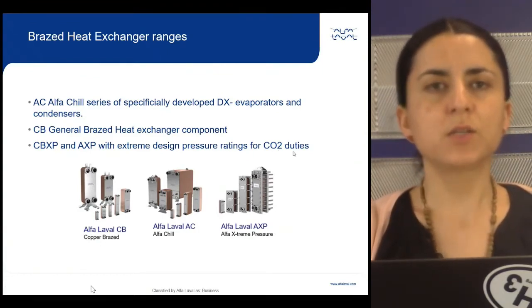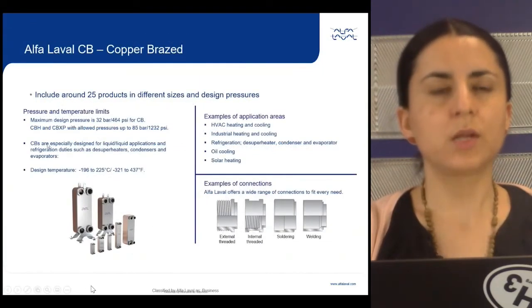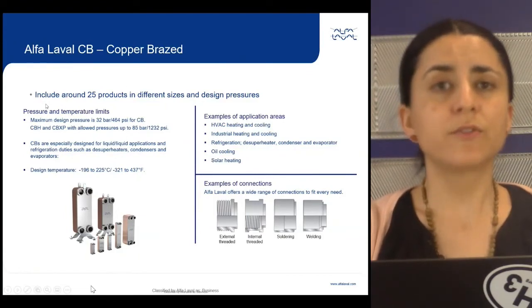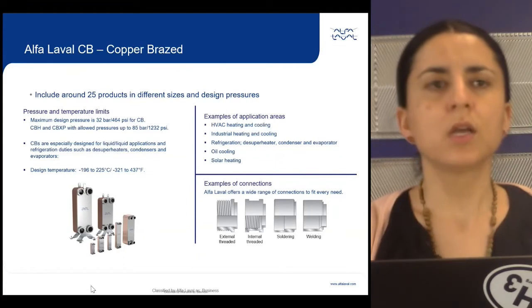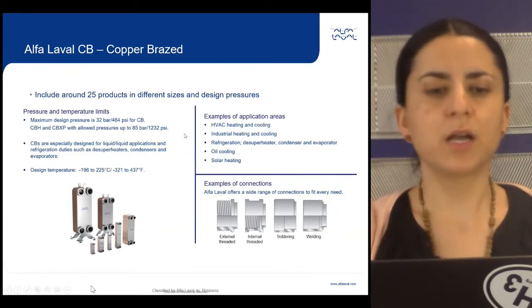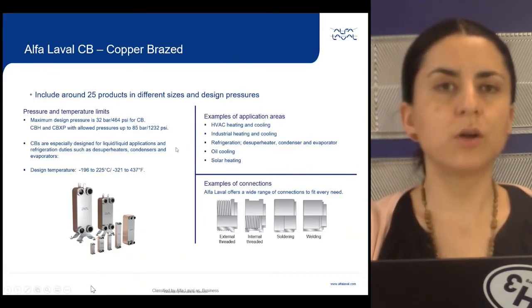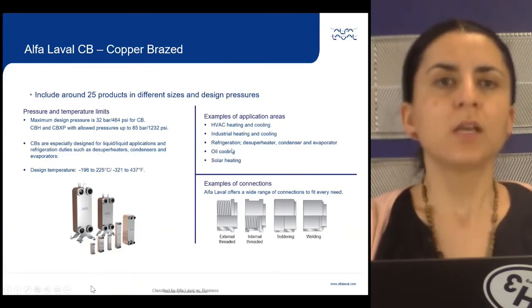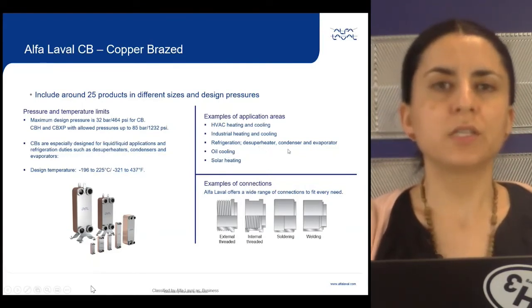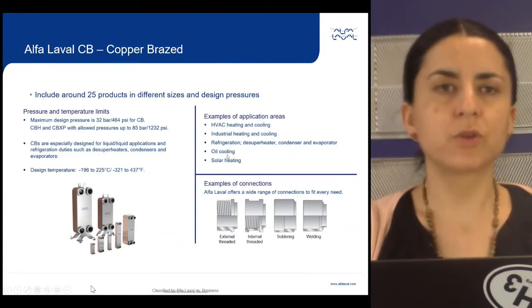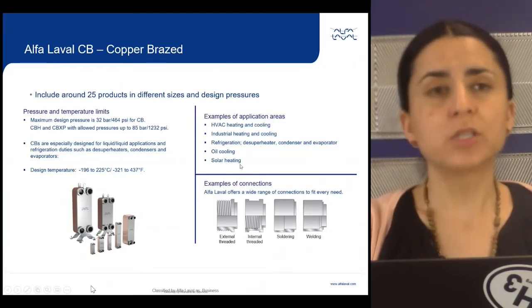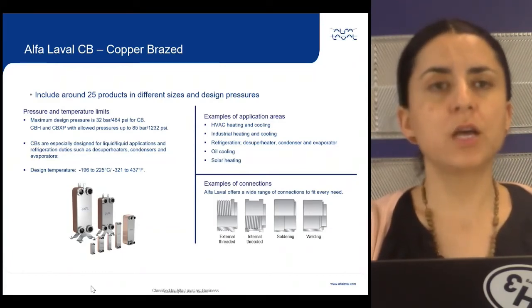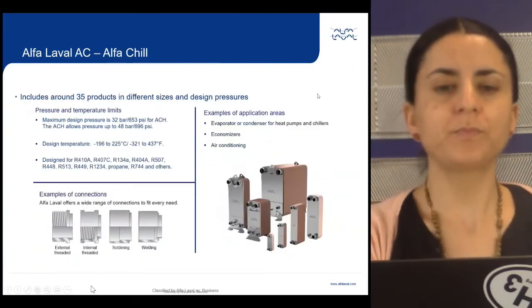Alfa Laval CB is one of the largest product lines that we have and is used for several applications, mainly liquid-to-liquid applications, for instance, for HVAC, industrial heating and cooling, as well as refrigeration as a desuperheater, condenser, or evaporator. There are products in different sizes, channel volumes, and pressure ratings. It's important to mention that all of the units have CRN available.